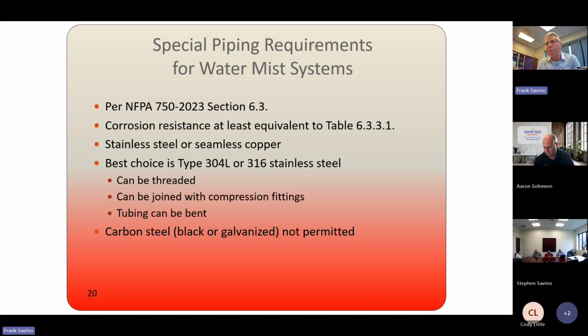The other thing that was a little bit of a hassle and expense was the electrical power supply requirements for an electric pump. It has to be tapped ahead of the main breaker. So that got a little bit expensive. But overall, it was a good application for water mist, where you didn't have the water supply for sprinklers, but we had it for water mist. So I just share that story with you, especially for JLRD. They do a lot in the healthcare industry. And you can really apply this to any situation where you don't have the water supply to support a sprinkler.